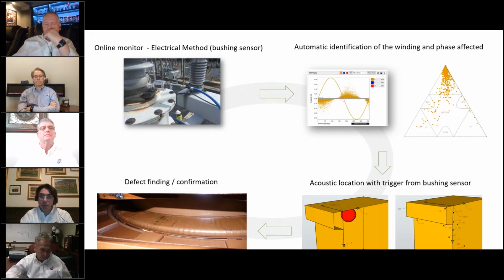In that situation they are extremely useful, especially if, like in this case, you use the bushing adapter as electrical trigger and the acoustic sensors for the triangulation, triggered by this electrical sensor. So you don't use the all-acoustic method. In this case, I would say the acoustic sensors are really helpful for transformers in order to pinpoint, with reasonable accuracy, the main source of the issue in the transformer.